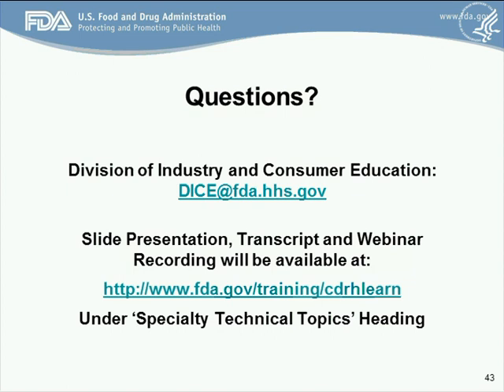The next question comes from Heather Nigro of Next Stage Medical. She asks whether the guidance indicates that FDA will inspect the facility for those utilizing a novel sterilization technique — is this a mandatory inspection similar to a pre-approval inspection for a PMA, or could you obtain 510K clearance without an inspection taking place? The response: this may be a case-by-case situation, depending on how much information comes in with the submission and how much is already known by the agency. The guidance does lay out both options.